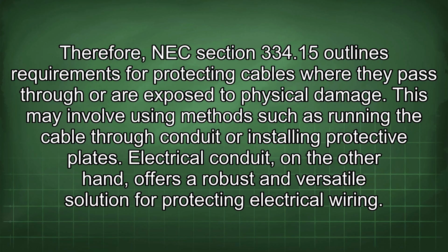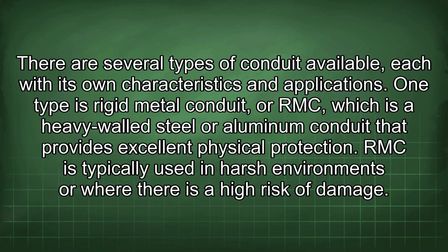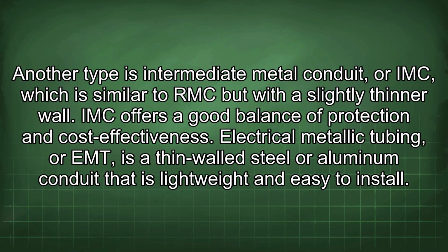Electrical conduit, on the other hand, offers a robust and versatile solution for protecting electrical wiring. There are several types of conduit available, each with its own characteristics and applications. One type is rigid metal conduit, or RMC, which is a heavy-walled steel or aluminum conduit that provides excellent physical protection. RMC is typically used in harsh environments or where there is a high risk of damage. Another type is intermediate metal conduit, or IMC, which is similar to RMC but with a slightly thinner wall. IMC offers a good balance of protection and cost-effectiveness.